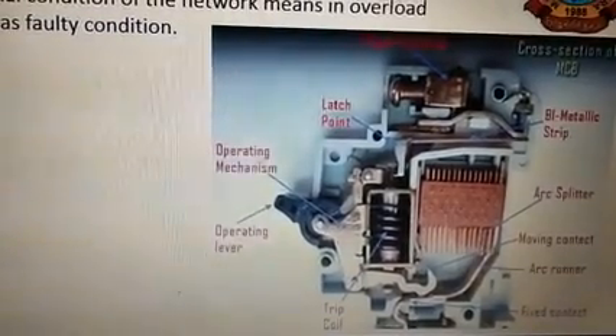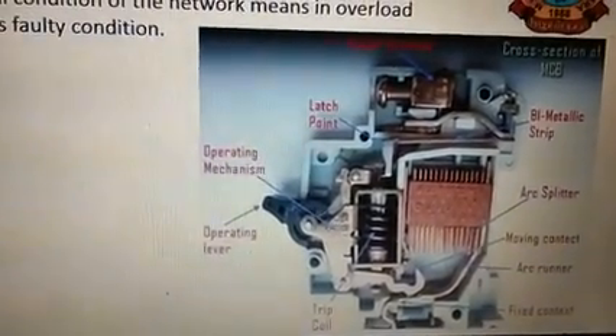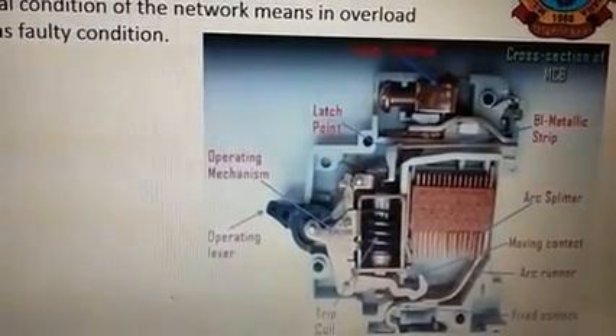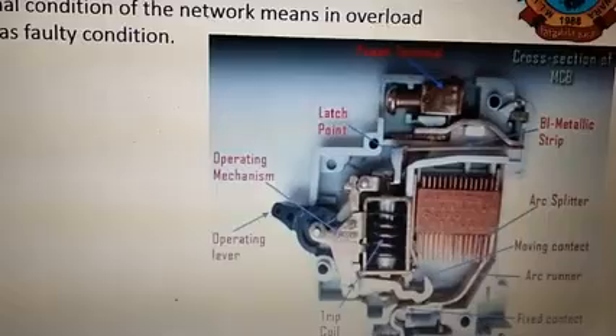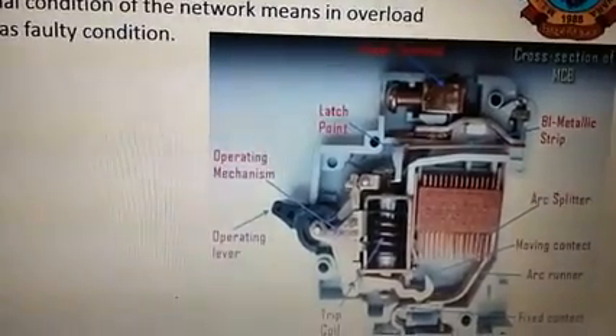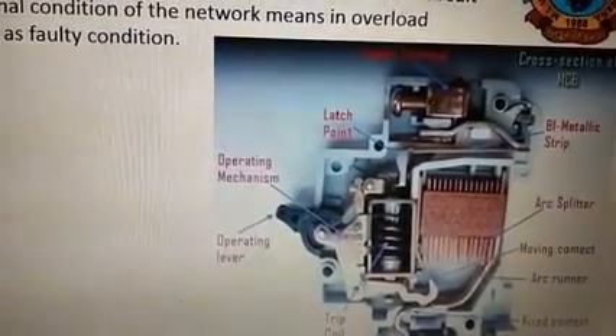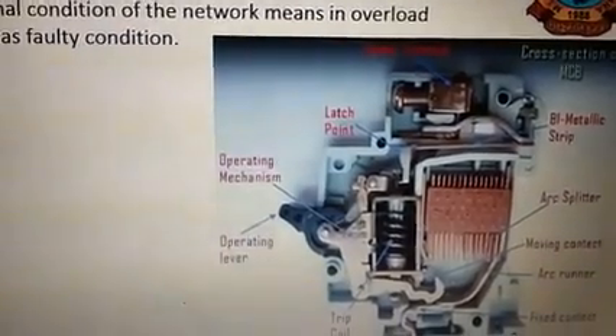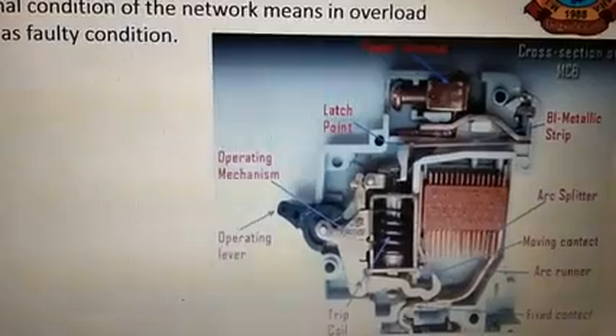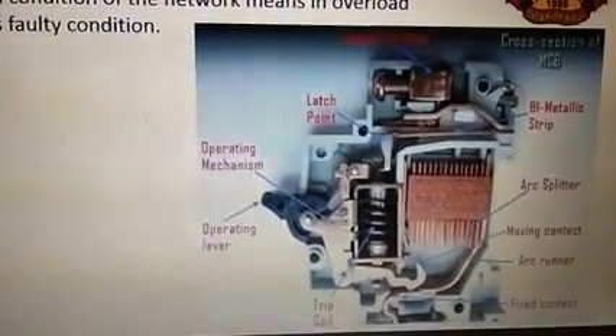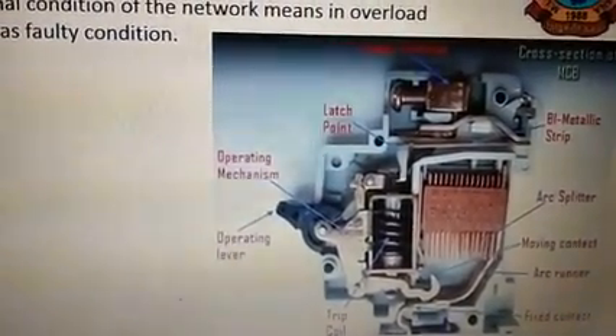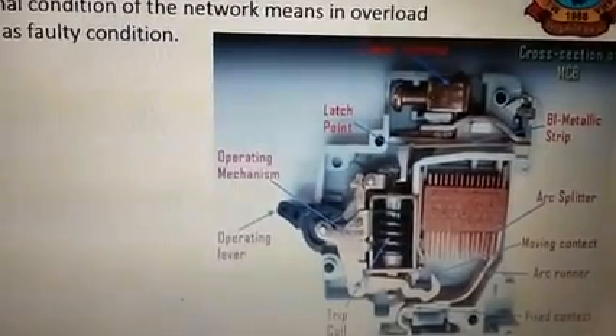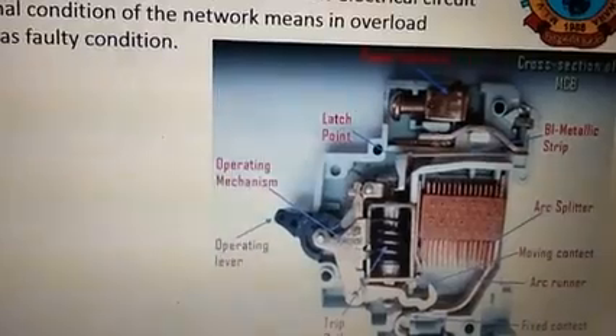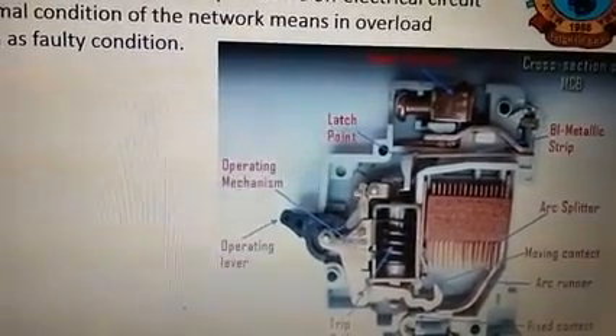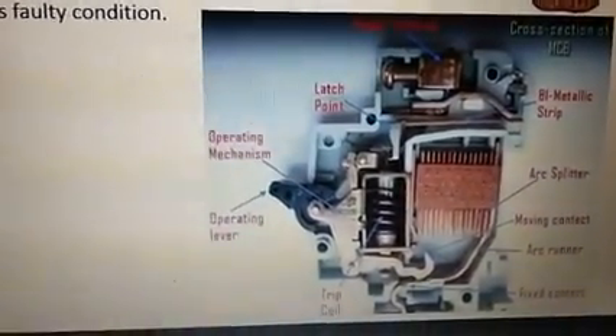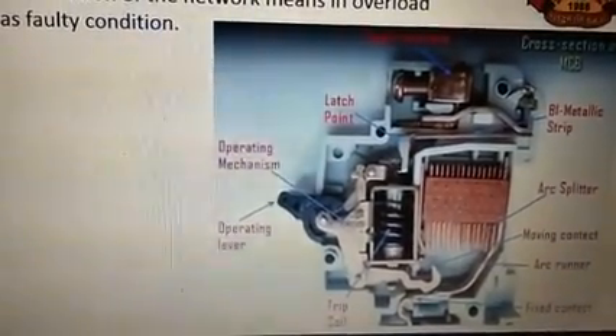The second is the trip unit. The trip unit of the miniature circuit breaker is responsible for the proper working of the MCB. There are two main types of trip mechanism provided in the MCB. A bimetal provides protection against overload current and an electromagnet provides protection against short circuit current.